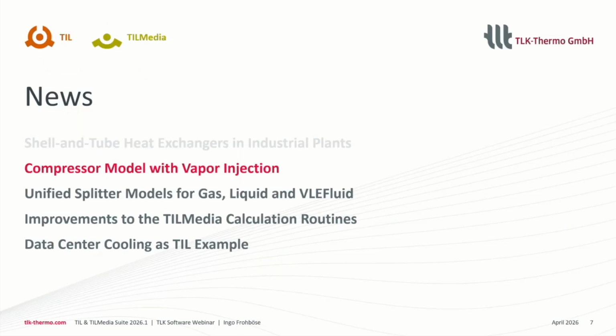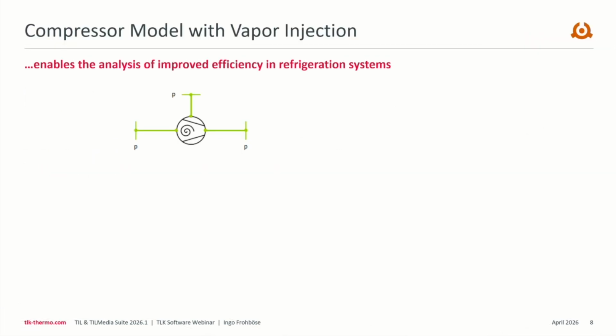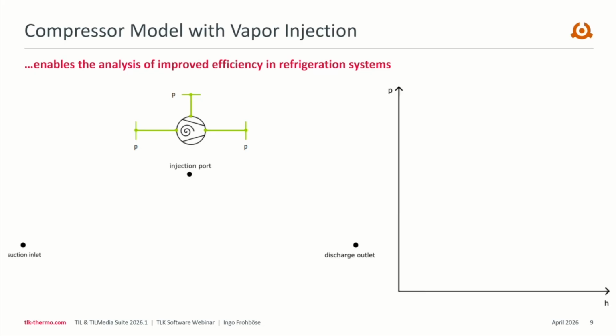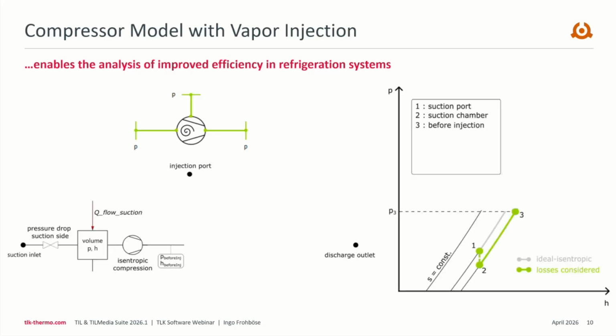Okay, next I'm looking into the compressor model with vapor injection. Typically these models have a third port, and they enable the analysis of improved efficiencies in refrigeration systems. So let's go step by step from the suction inlet on the left side in a pH diagram, which is shown here on the right. Our loss-based or physics-based models typically have a suction side pressure drop, and then we have a suction volume here on the left side, an isentropic compression.